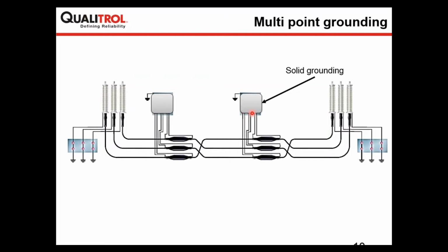So that's why, whenever we perform online partial discharge measurement, it's very important to know the cable earthing scheme, or sometimes it's called the cable grounding scheme. Whenever you are doing online partial discharge measurement, there can be a scenario where the remote end of the power cable will be open and it will be grounded with the help of a sheath voltage limiter.